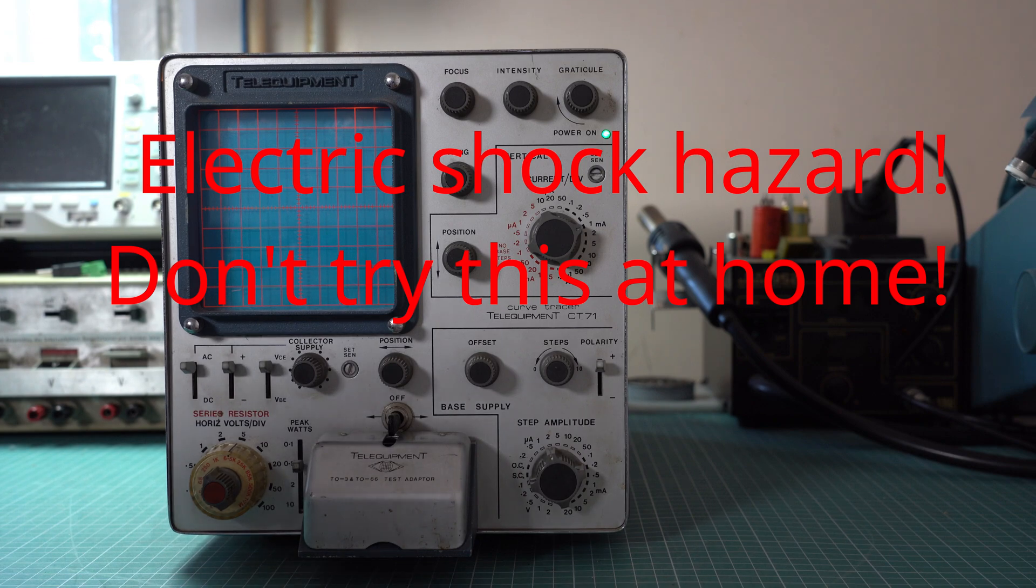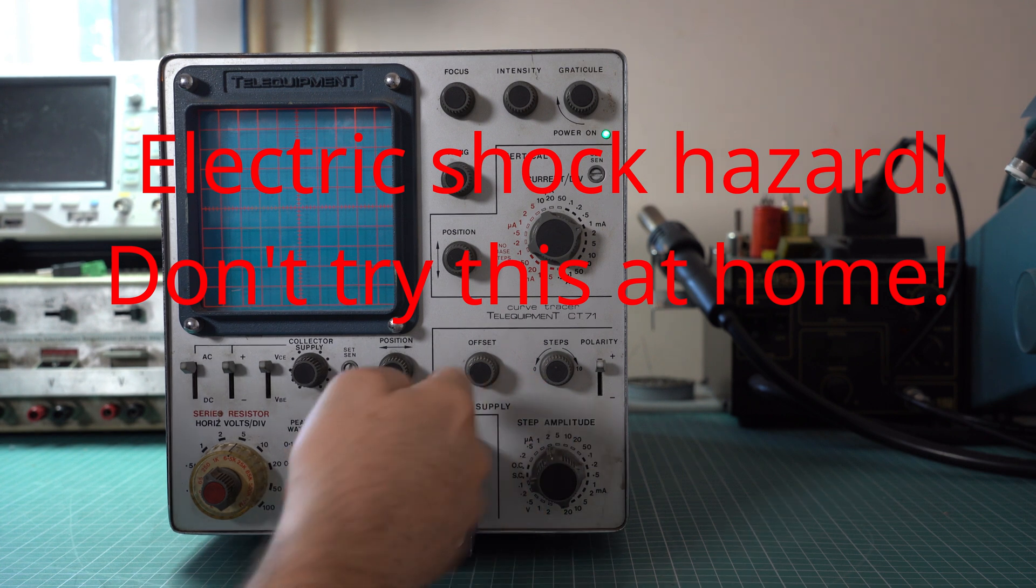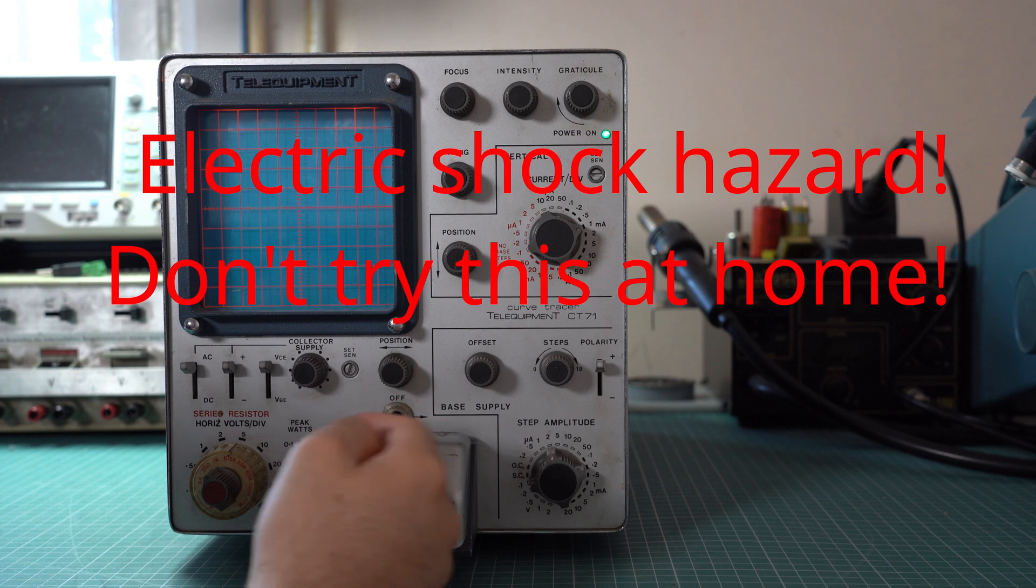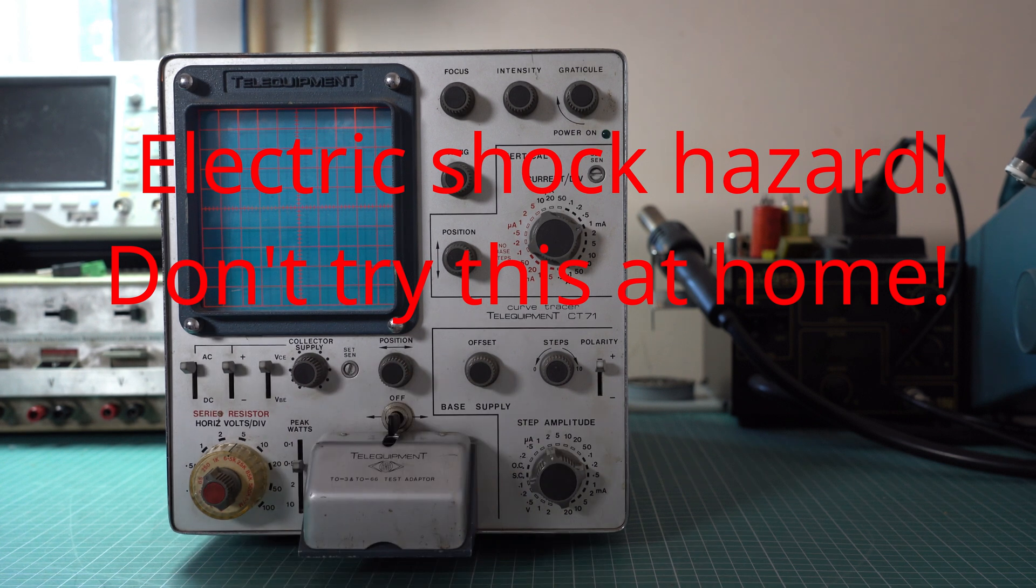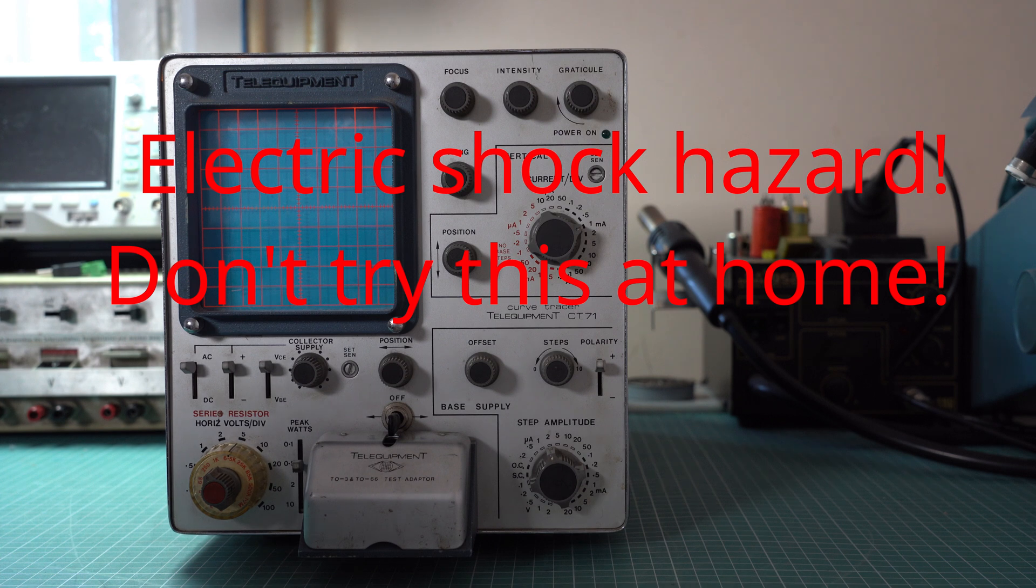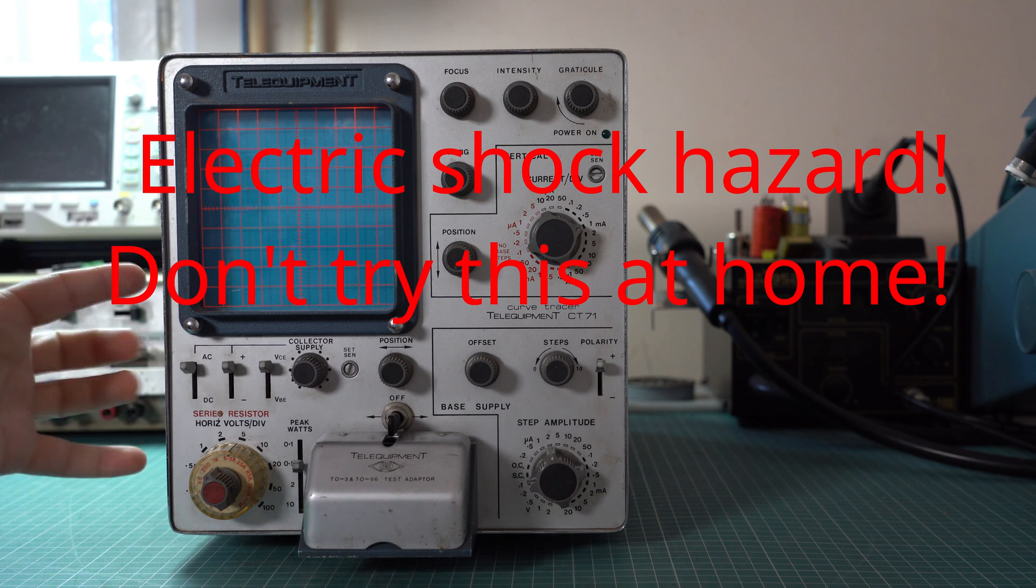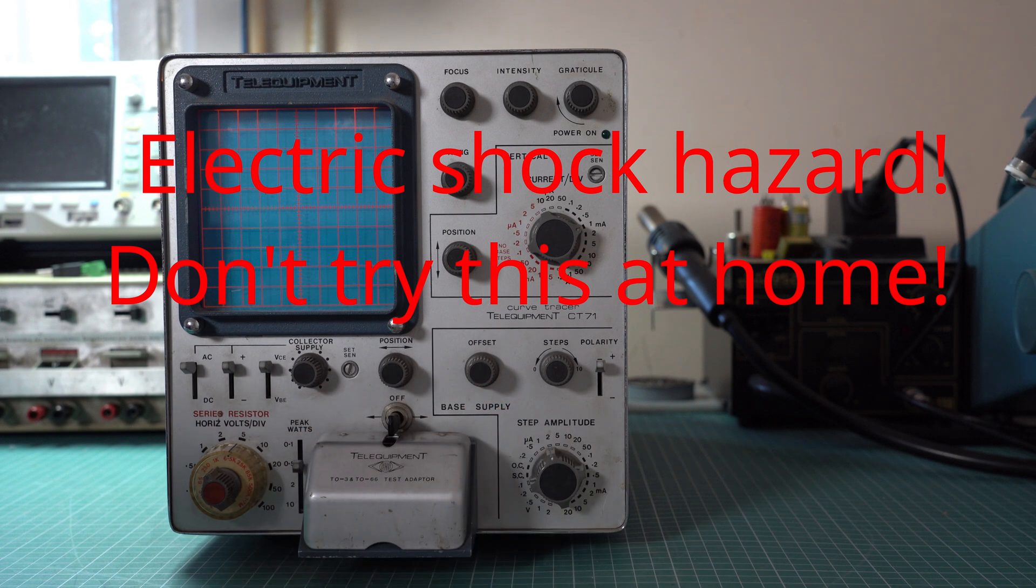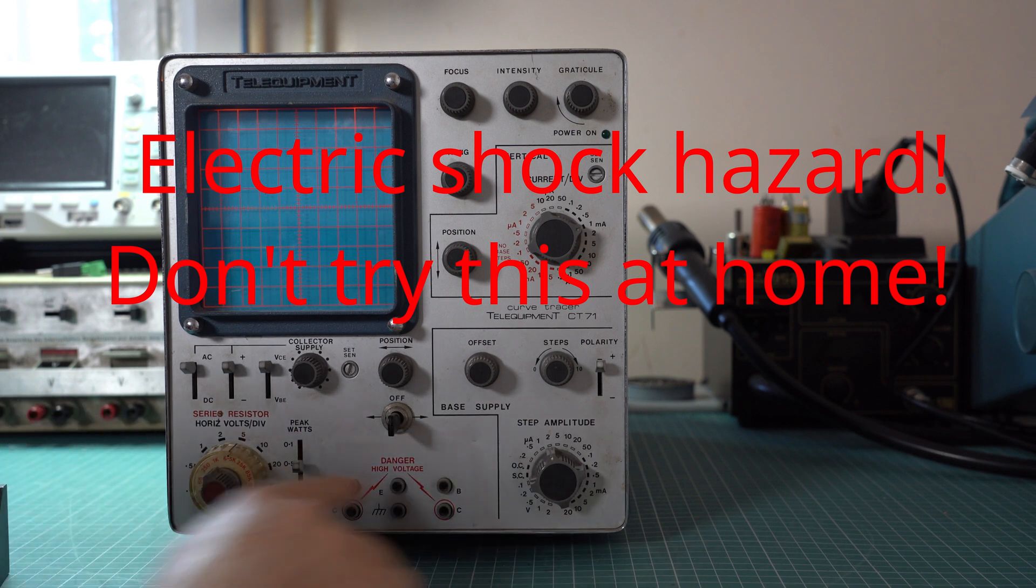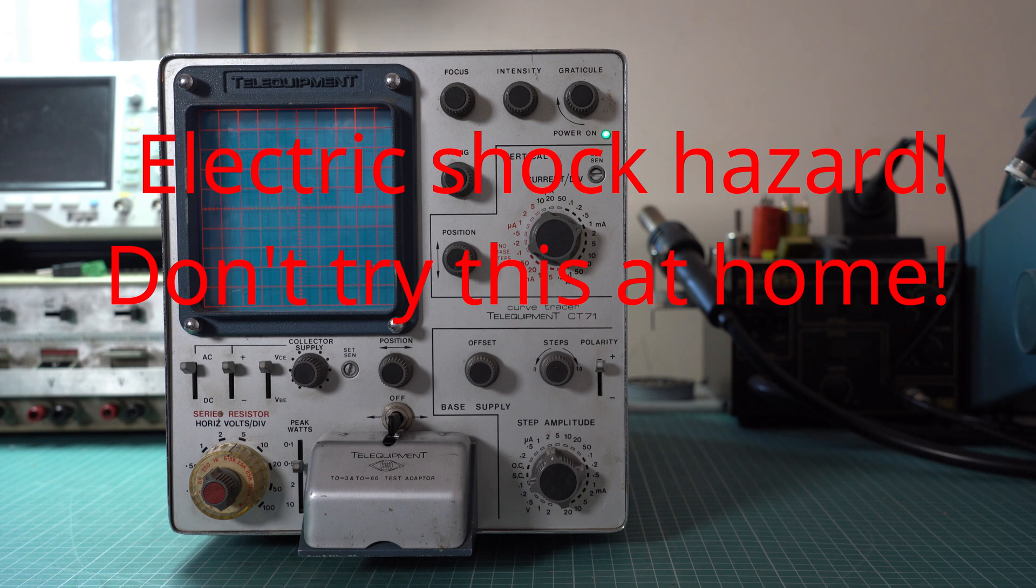But first of all let's talk about safety. There is a good reason why this fixture has a cover. Once we select one of the two DUTs inside we cannot open the cover. That's because a Curve Tracer is a really dangerous piece of test equipment. In order to produce IV curves it has to apply a test voltage, and that test voltage can go all the way up to 1kV in the case of this device. This is really dangerous. You should only use this fixture or be very careful if you improvise something. This is why it says danger high voltage right here. Please don't try this at home.